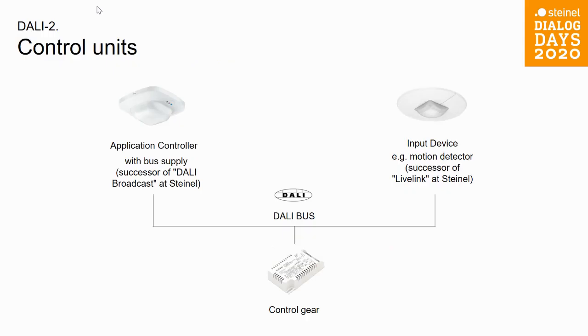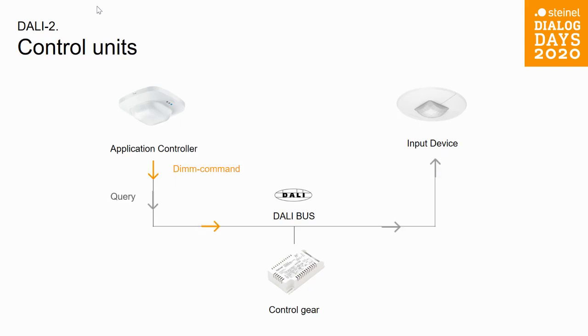The difference between application controller and an input device. They both speak back to the control gear ultimately. So the application controller is with a bus supply. This is the successor of the DALI broadcast sensors at STEINEL. And an input device, such as a motion detector, is the successor of the Livelink sensors at STEINEL. So the application controller is sending a command, in this case a dim command, which is sending straight to the control gear.